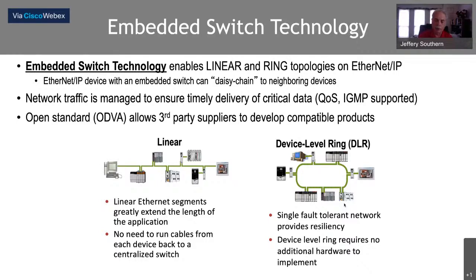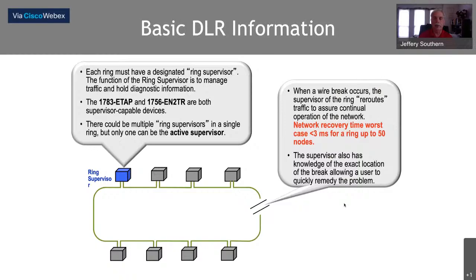Rockwell developed this specific ring topology because it can self-heal within 3 milliseconds, meaning for up to 50 nodes on a DLR ring, it can self-heal if a device is unplugged or a cable gets cut. Typically the IO is never even disrupted - it never has a problem. In some ring topologies used elsewhere in plant IT, it could take up to 30 seconds for the ring to heal itself, and you can't take the network down that long. That's why a DLR ring is so important for media resiliency in an industrial network.